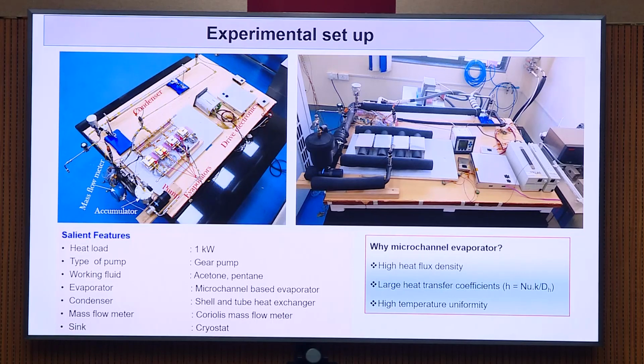Actually, you can see we have used multiple evaporators here. These are 4 evaporators we have connected in parallel, and the pump will be supplying the liquid to these 4 evaporators, and the vapor travels to the heat exchanger, like a condenser, a shell and tube heat exchanger, and then the fluid comes back to the evaporator via a pump and an accumulator. Here we have used a gravity based accumulator. However, for the spacecraft we will be using a two-phase accumulator. And we have done several tests on this, and we have got good results. This is the insulated one, the right side gives the insulated.